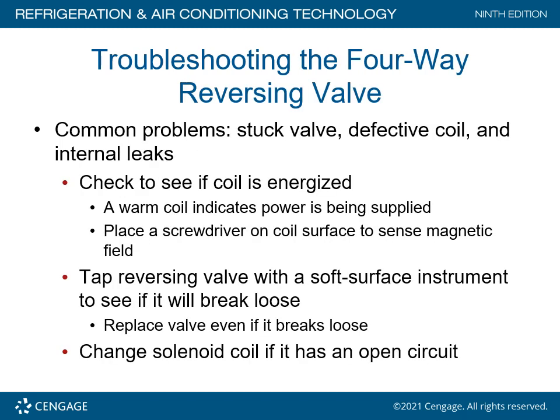Troubleshooting the four-way reversing valve: common problems are stuck valves, and I hate to say it, that is a very common problem, a defective coil, which happens once in a while, and internal leaks. Check to see if the coil is energized. If you have a heat pump that's not working correctly, the first thing you want to do is see if you've got 24 volts to the coil, depending on whether it's supposed to be energized or de-energized. A warm coil indicates that power is being applied, so you could just do the touch and feel. Place a screwdriver on the coil surface to sense the magnetic field.